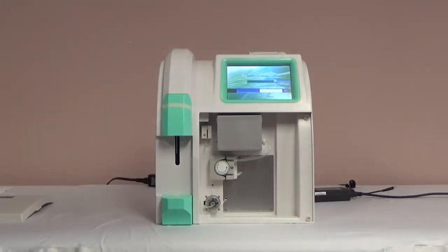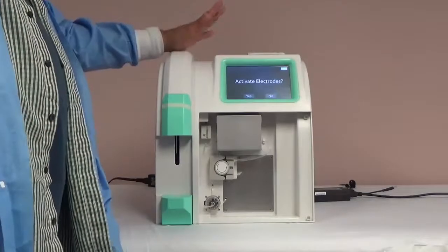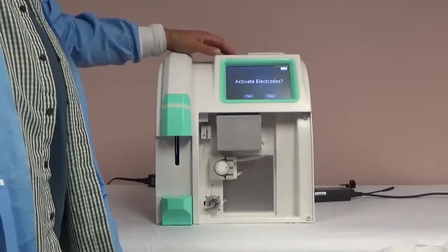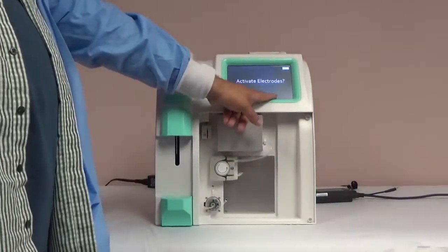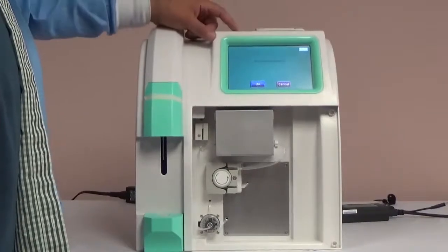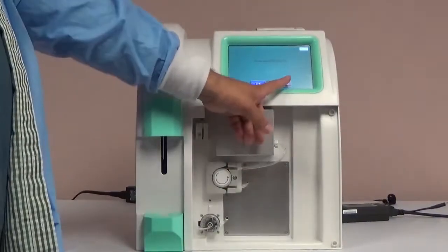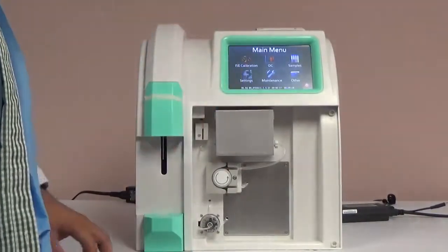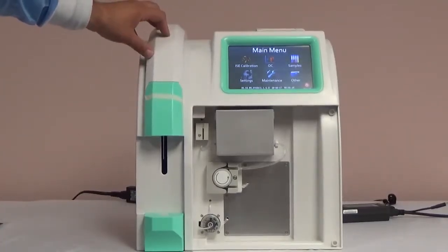It will check for and detect the pack. When the analyzer reads the pack, the first message to show up will ask you to activate the electrodes. Before you activate the electrodes, you will need to prime the pack, so select No on the screen. When the analyzer prompts you to calibrate, hit Cancel. This will bring you to the main menu. Select Maintenance, then Replace Pack to prime it, then select OK.